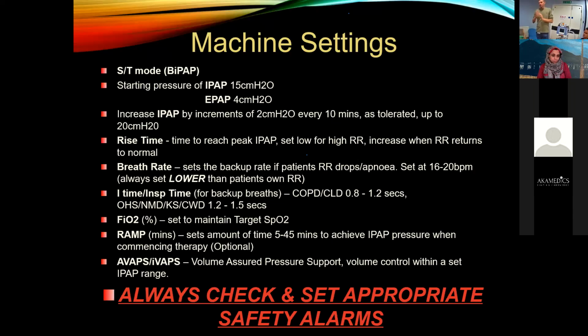So our target pressures to start therapy with BiPAP would be an IPAP of 20 and an EPAP of 4. Now, some of the other settings that we've got within BiPAP on our devices, for both your ResMed and Respironics machines: rise time. Rise time is a time we want the machine to use to reach the peak IPAP.